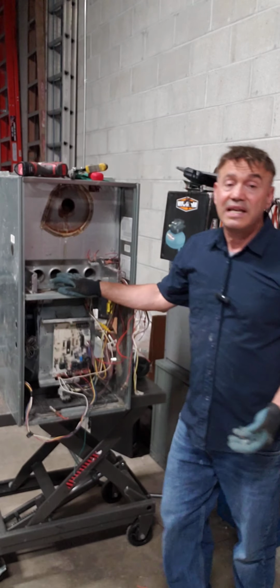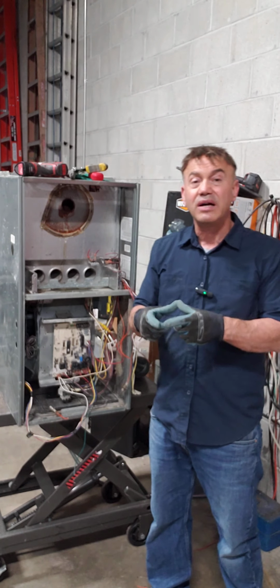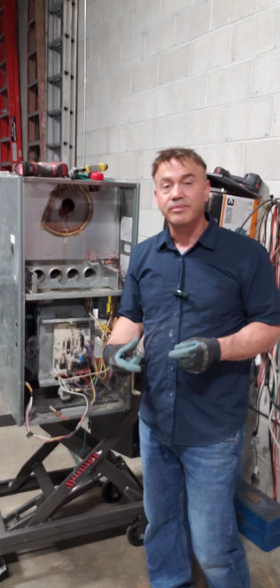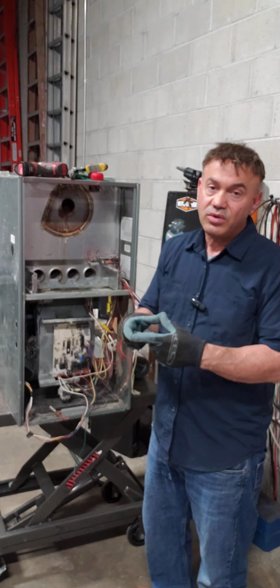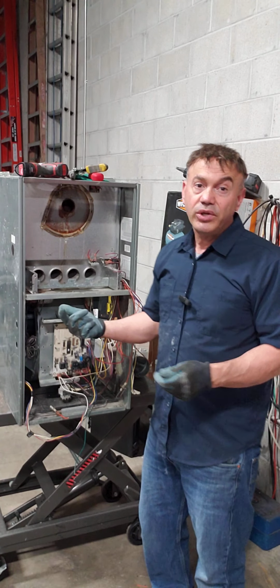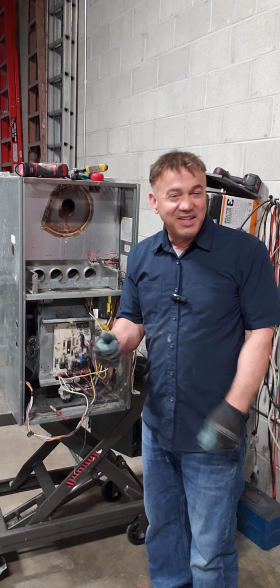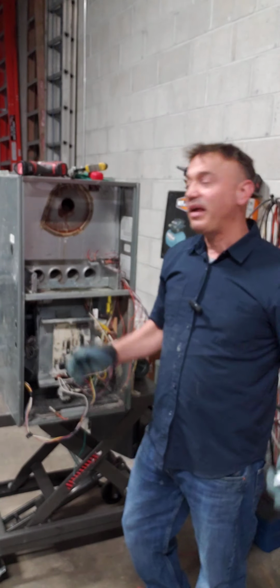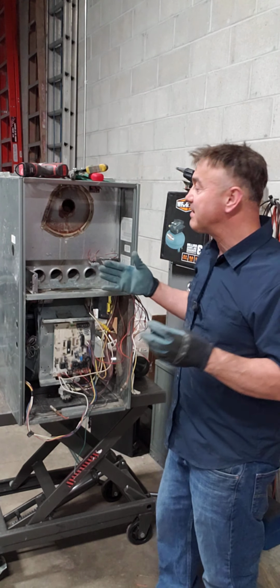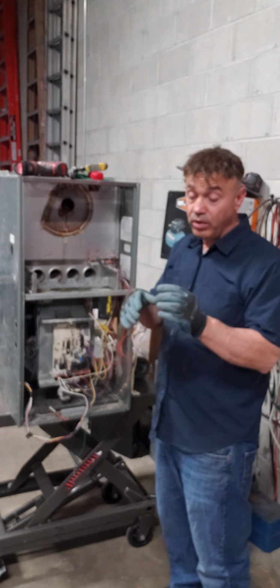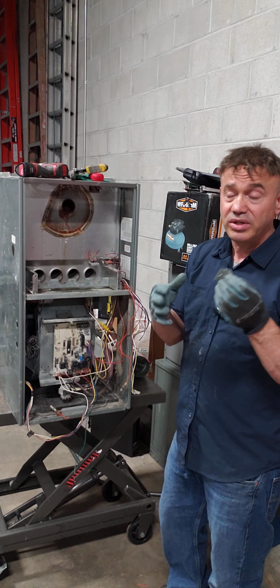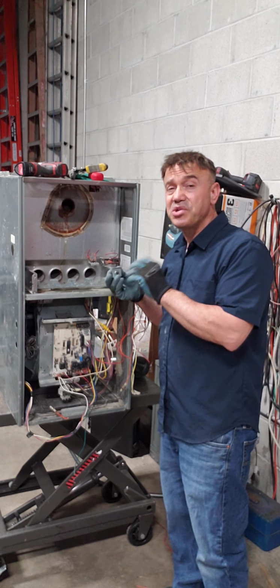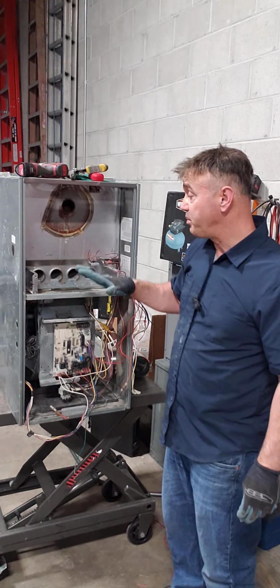If the gas is very strong, it's like cooking with a small pot on the biggest burner in the oven - a pot that's only for two eggs, but you're using the biggest burner and the flame is crazy. That's often why this rollout switch gets bothered - hey, it's too hot. So the gas pressure has to be adjusted. Again, it could be many things.